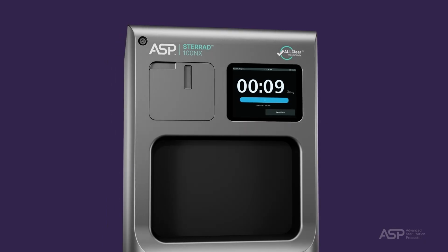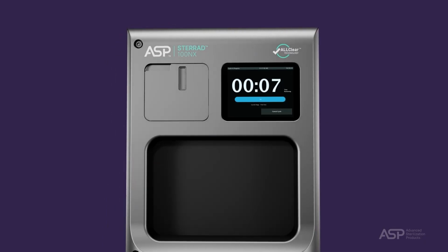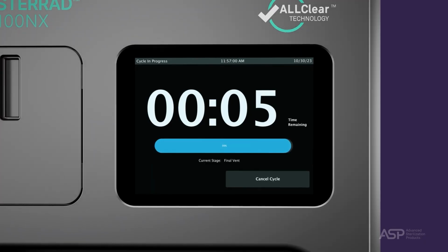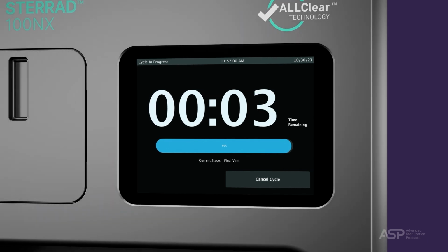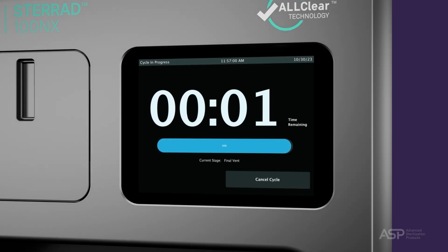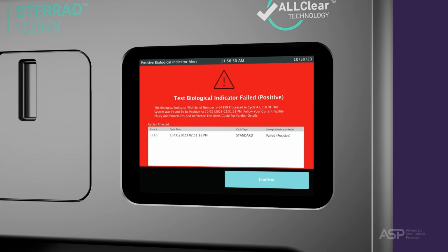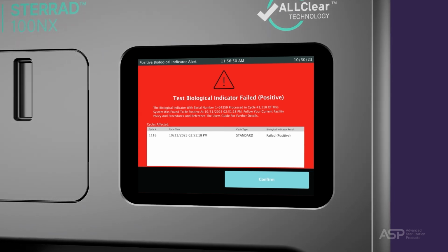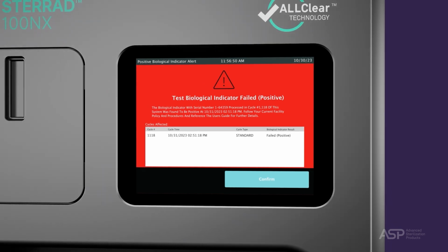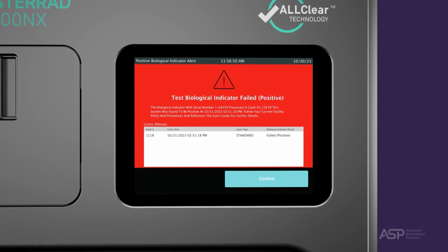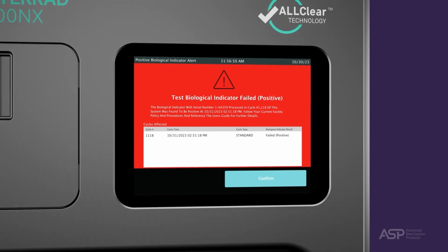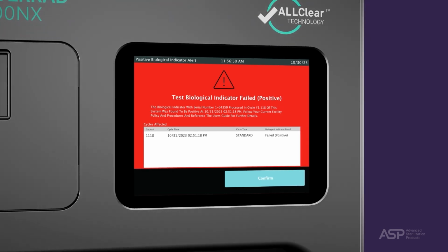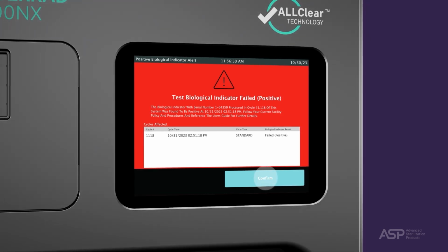Note that if the STERRAD Velocity Reader detects a positive test biological indicator when the sterilization cycle is running, the notification screen will only appear after the completion of the sterilization cycle. All known potential loads since the last negative test biological indicator results are listed on your screen. Touch the Confirm button on the screen to acknowledge the test BI used in the load has a positive result.